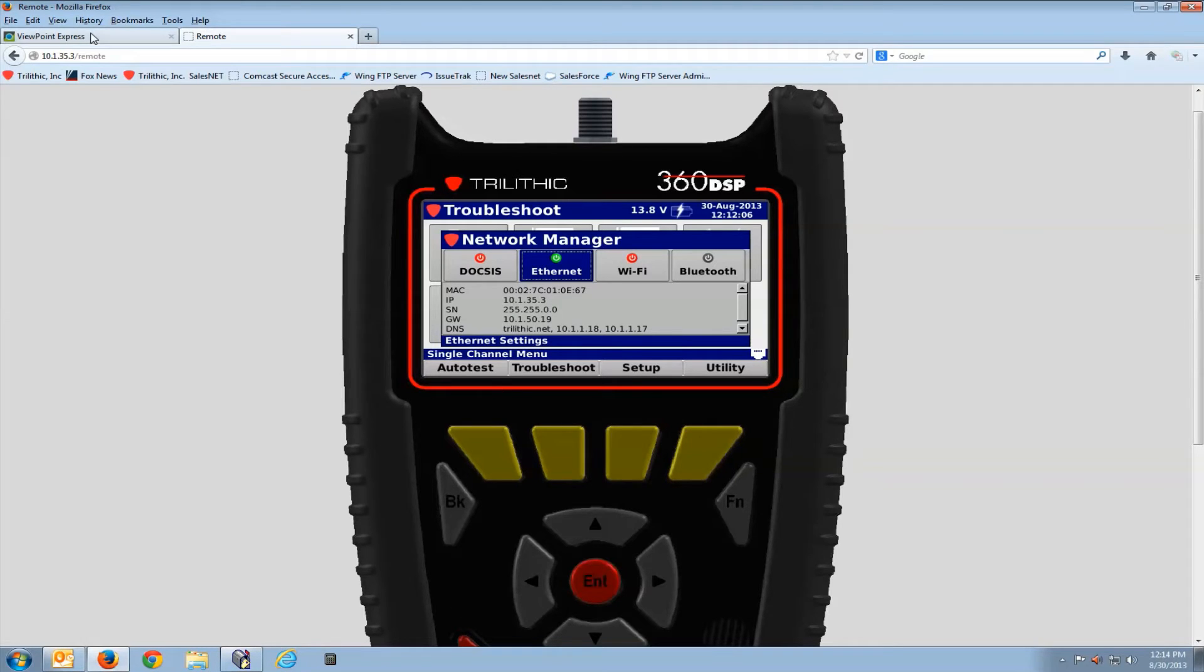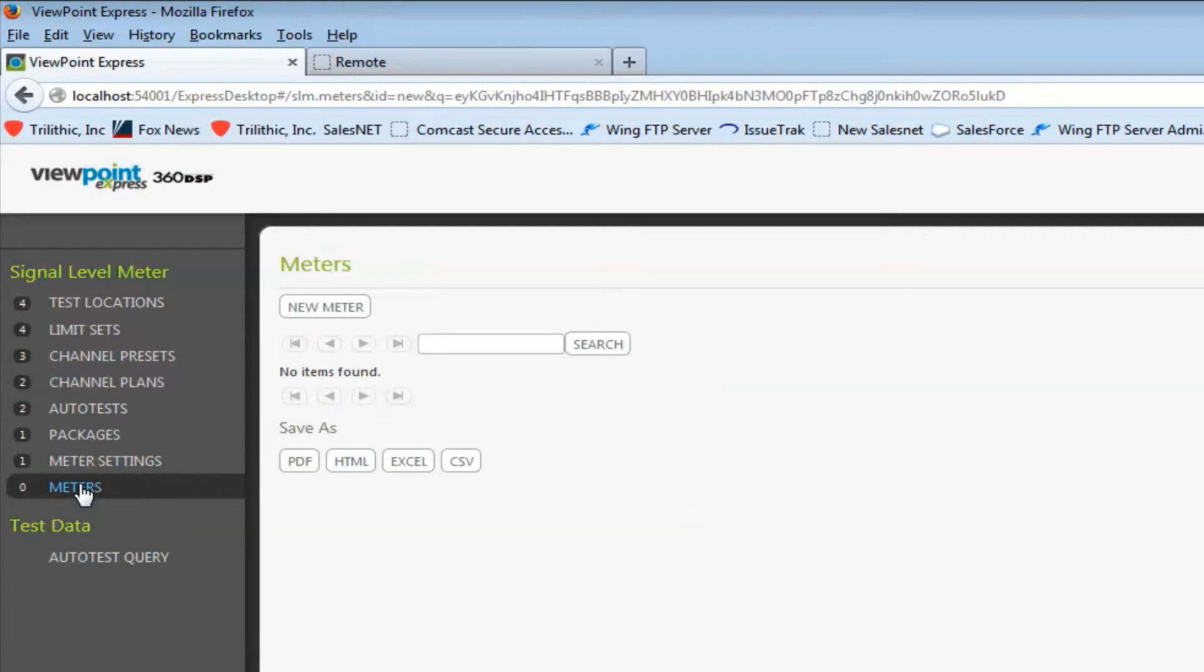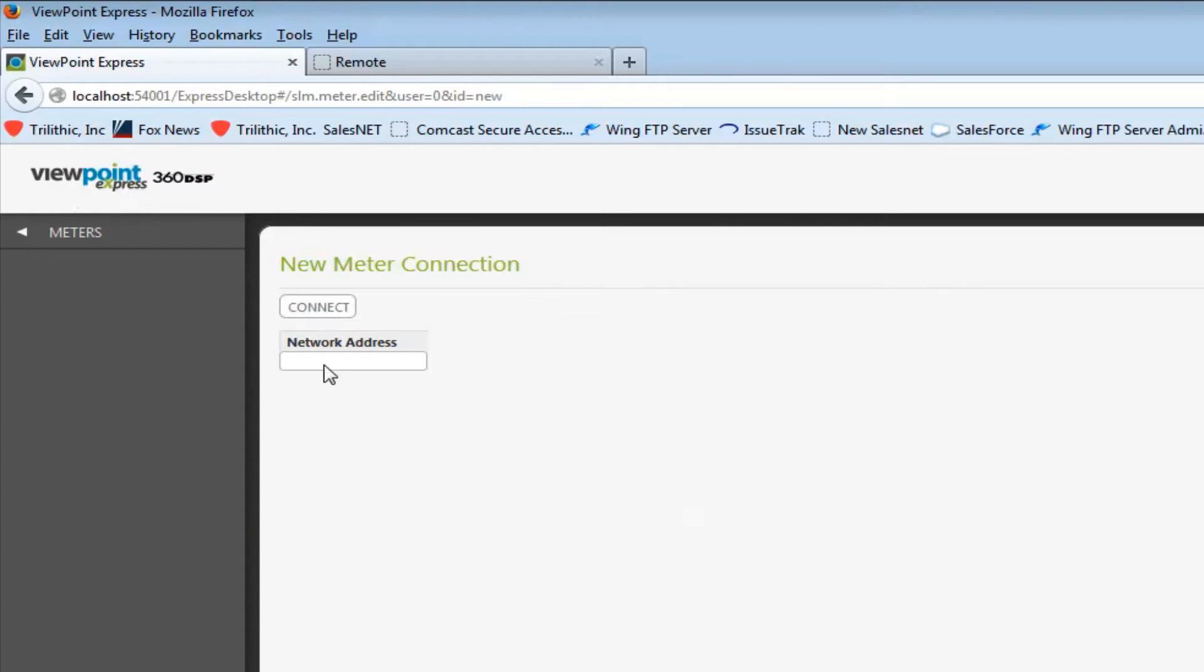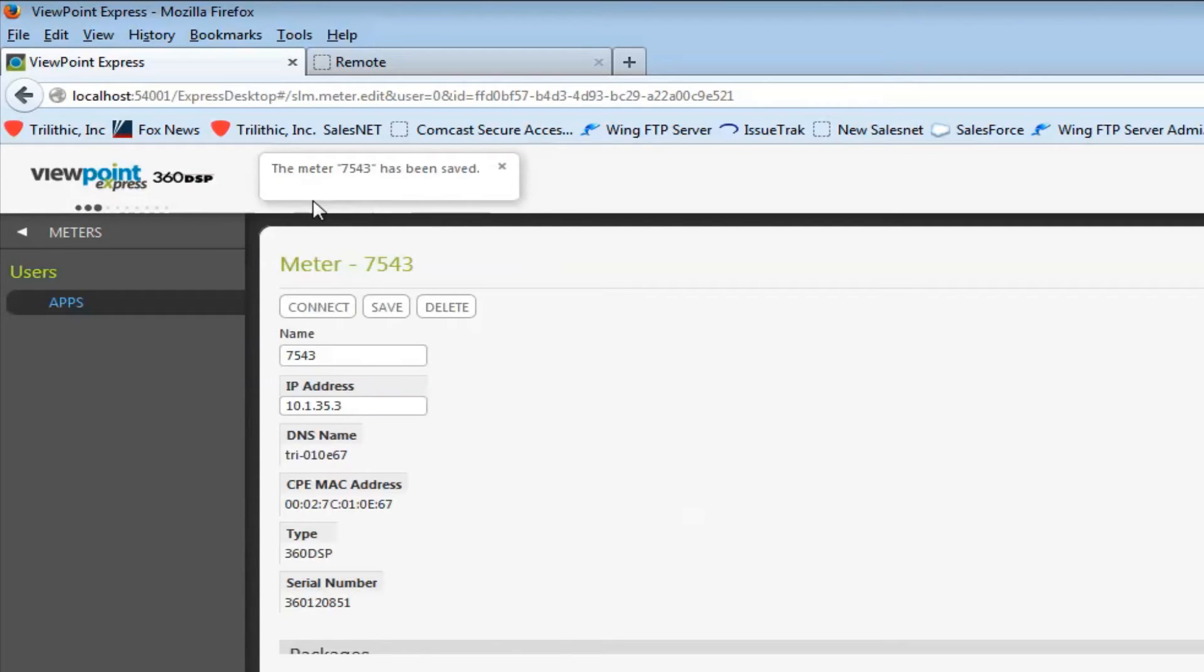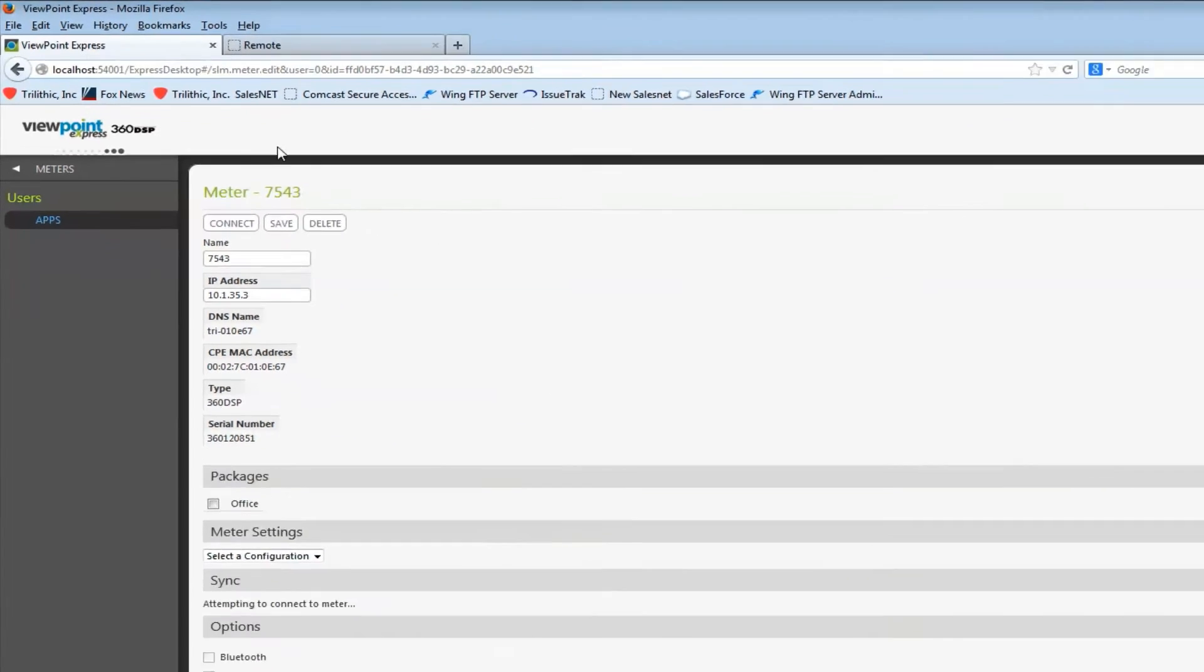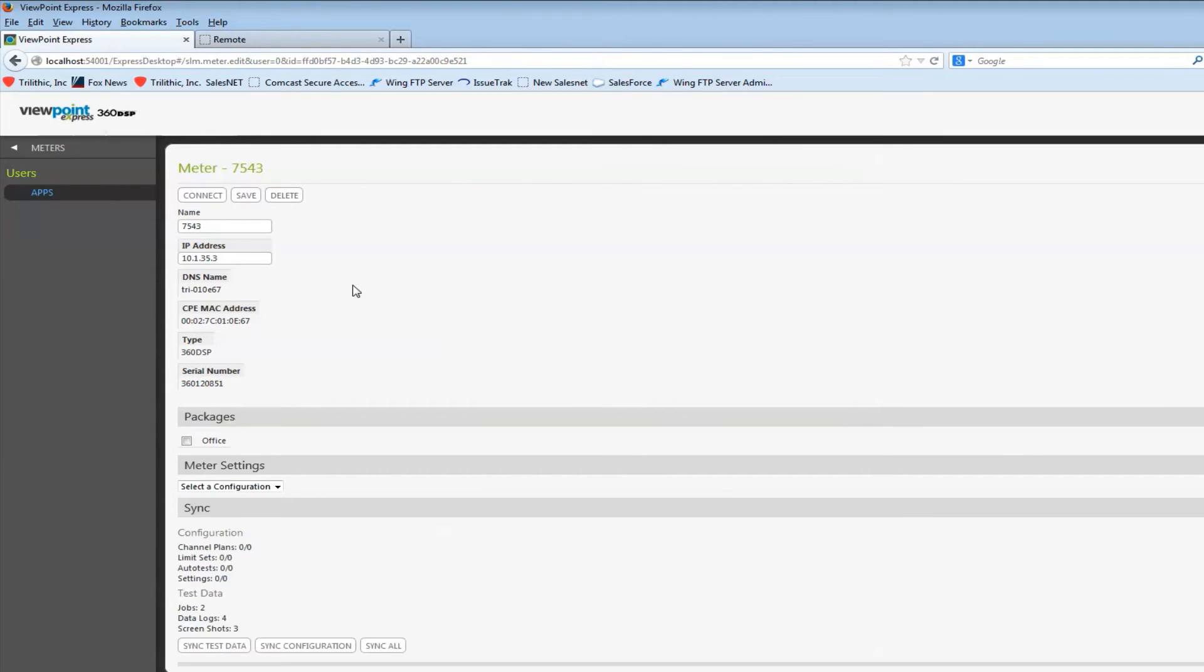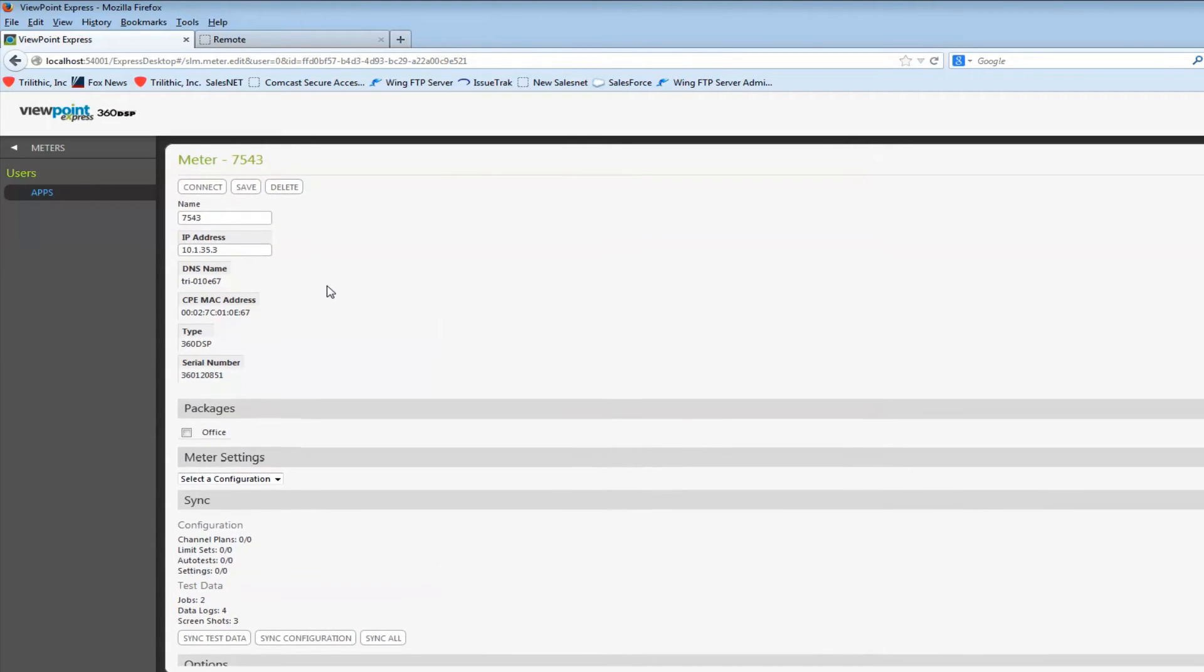In the Viewpoint Express software I'd go to the meter tab, select new meter, simply type in the address 10-1-35-3, and select connect. I'll have some progress information along the top here. Once the meter connects you will see this screen which has some of the specifics on the 360.